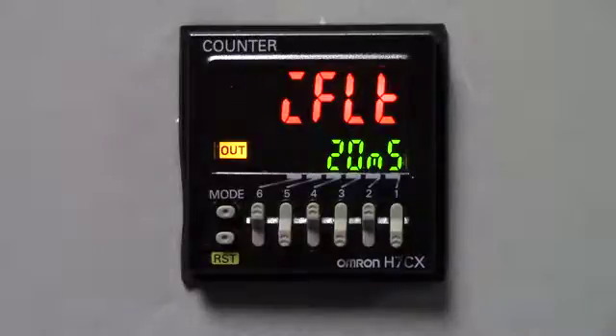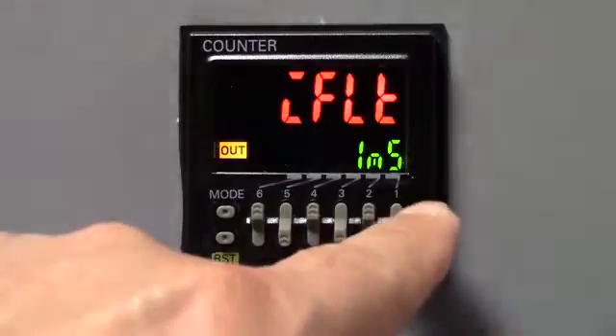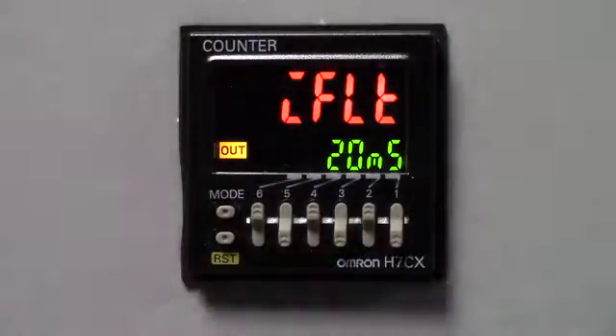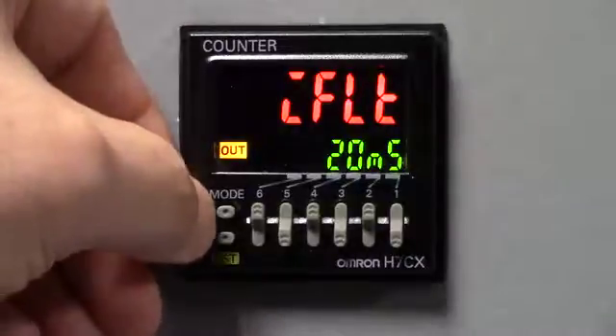IFLT. This stands for Reset Input Signal. As we had done with the counting speed, there's two speeds to choose from here. There's 20 milliseconds or 1 millisecond. For an application like what we are going to do, using a basic switch, a limit switch, or a push button, we could keep it at 20 milliseconds. You would use the 1 millisecond for very high input. Let us now proceed to the next mode.